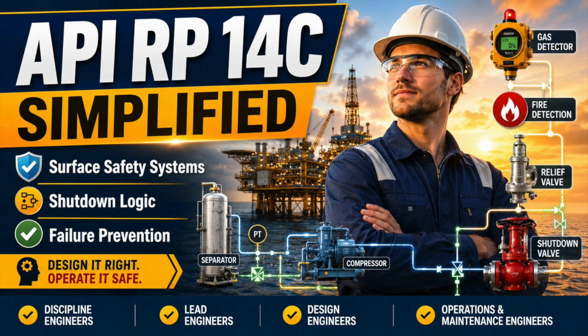Pipelines require another level of thinking because the inventory beyond the platform can be enormous. An incoming pipeline can continue feeding the facility. A departing pipeline can backflow toward a rupture. A bidirectional pipeline cannot depend on a simple check valve. Shutdown valves must minimize exposed inventory. Check valves must minimize backflow where one-way flow exists. Remote sources and local actions must be coordinated. A pipeline is not just another process line, it is a stored energy system connected to your platform.